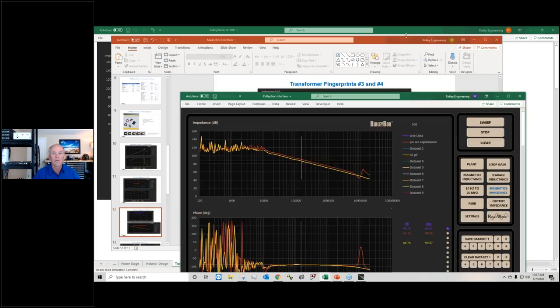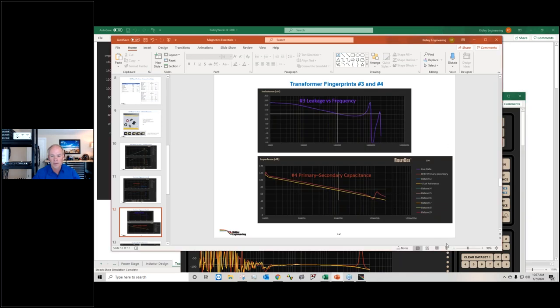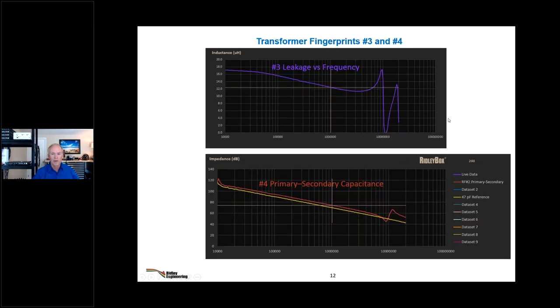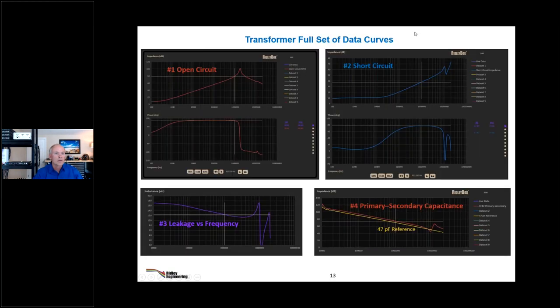Okay, so what do we have now? Back to our transformer fingerprints. For me, this is a full set of data curves for a transformer. You're going to measure open circuit gain and phase, short circuit gain and phase, and leakage versus frequency. This is the same data as the short circuit, but plotted just from 10 kilohertz to the maximum, watching the leakage change versus frequency. And then the final measurement on the transformer is the primary to secondary capacitance.